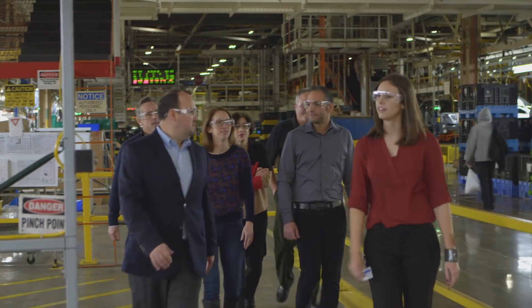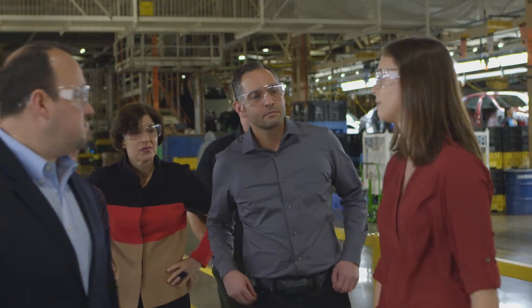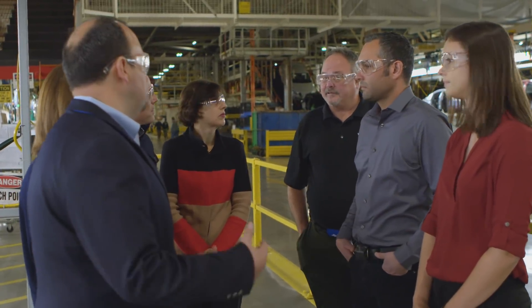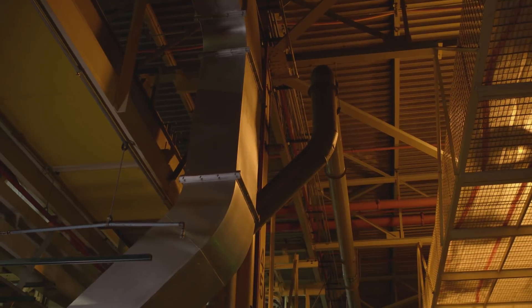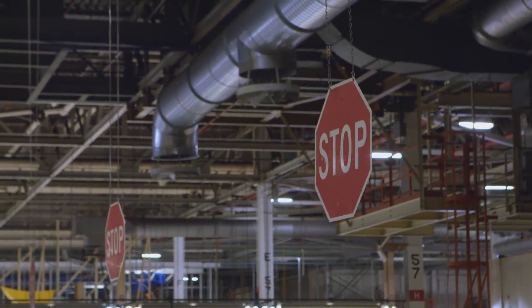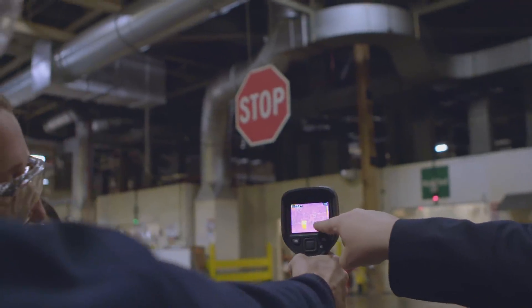So the production line has stopped here. In about another minute, we're going to see the lights turn off as well. The overhead lights you'll still see — it'll be enough for people to walk safely around — but we turn the line lights off automatically. Do you have any maintenance activity during the shutdown? Sometimes, yes. There you see the lights go off. During shutdown is the time where you can really hear any air leaks or see different things. I hear some right now. That stop sign is getting a ton of wind — look at that thing move. It's being pushed by something. Air vents up there — you've got a bunch of air vents in there. And you're seeing there's a different range of temperatures in each of those booths.